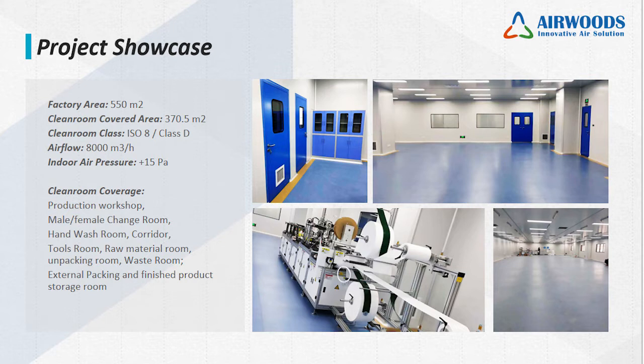On the top of the ceiling, you can see there are many diffusers to supply the air from the air handling unit. The total supply air is about 8,000 cubic meters per hour. And at the 2 side walls, there are some return air grills for indoor air circulation. The indoor air will go through the grills to the air handling unit, and the fresh air will mix with the return air, and after cooling, heating, or humidifying, it is supplied to the clean room areas.